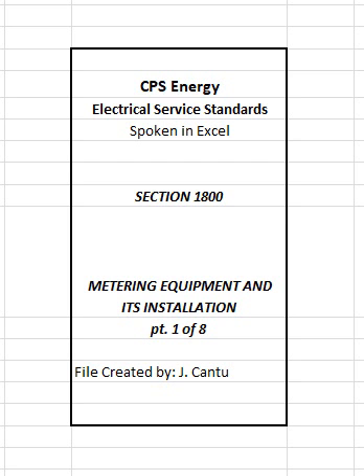1801 Unauthorized handling of metering equipment. Unauthorized personnel shall not handle CPS Energy metering equipment, possess seals, or break seals. Only CPS Energy personnel will handle, install, remove, rearrange, and seal/unseal electric metering equipment. Exception 1. CPS Energy may authorize customer to install instrument transformers in pre-approved enclosures/meter compartments.